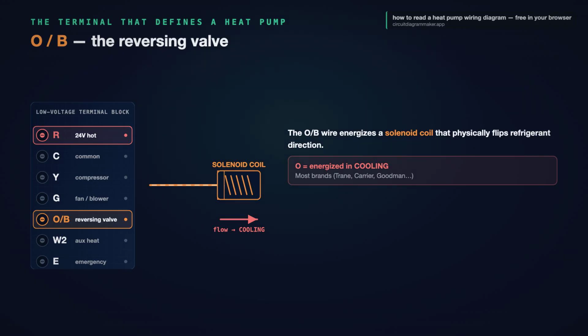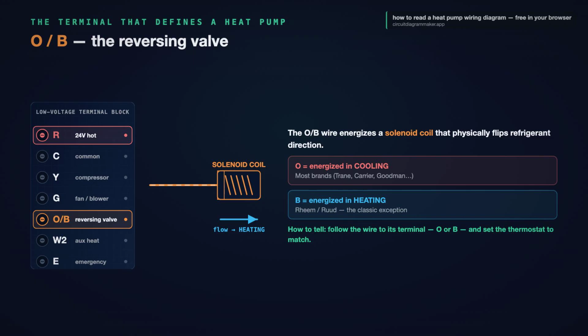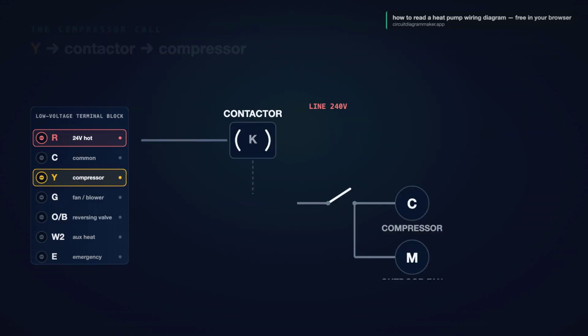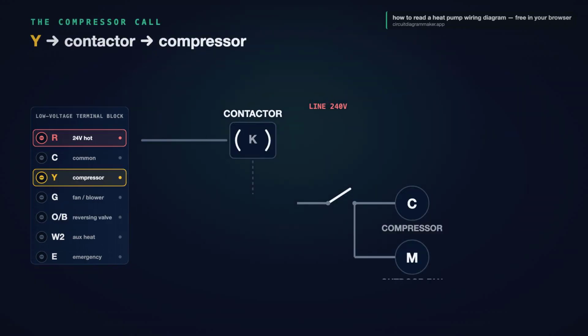On most systems, the O terminal is energized in cooling. On a few, Rheem and Ruud are the classic example, the B terminal is energized in heating instead. So how do you tell what you have? Follow the wire. If it lands on a terminal marked O, the valve energizes for cool. If it lands on B, it energizes for heat. Your thermostat has a matching O/B setting. Get it wrong, and the system blows cold when you call for heat.